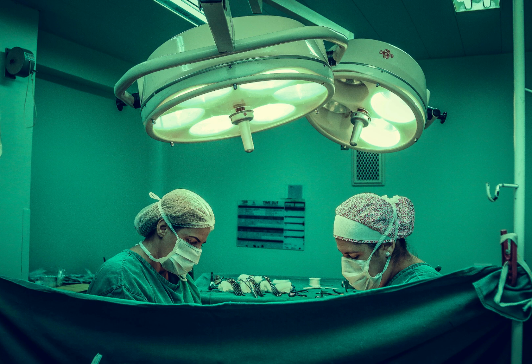Now, let's look at disposable versus reusable instruments. Disposable laparoscopic instruments are supposed to eliminate the risk of insulation failure, but they come at a steep cost, 9 to 19 times more expensive per procedure. So, while disposables reduce some risk, they are not a financially sustainable solution for every hospital. Reusable instruments are still widely used, but if we don't maintain them correctly and test them regularly, we're just passing the problem down the line.